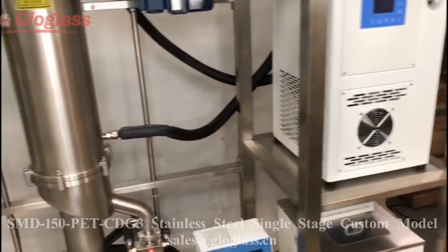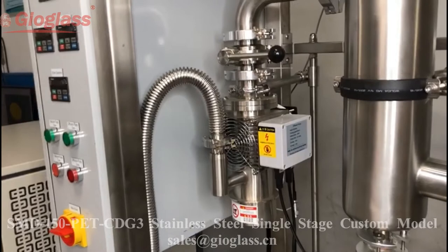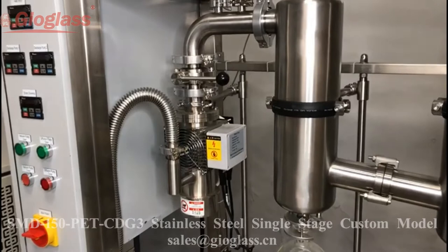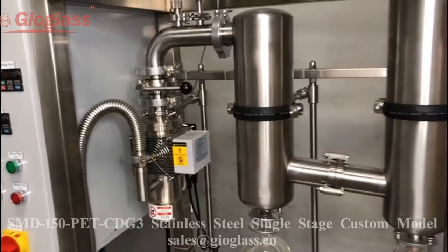D is for the diffusion pump. The diffusion pump can enhance the vacuum level to 0.001 mbar under no-load conditions.